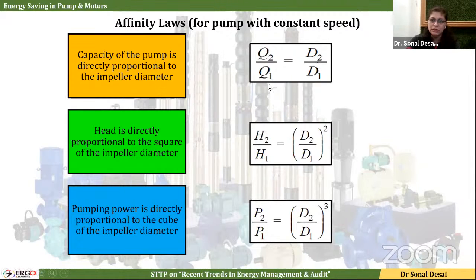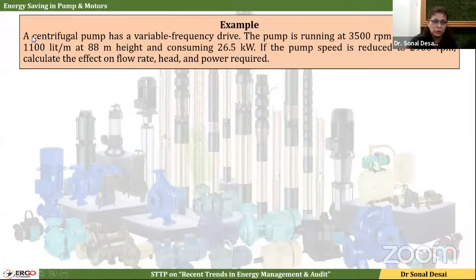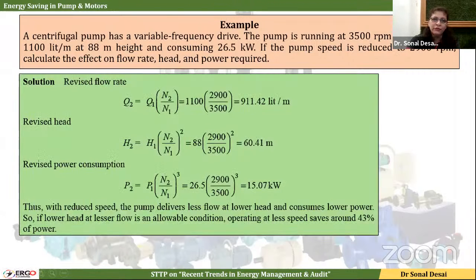If we reduce the diameter, the flow will be varied by a little, but it will have a huge, significant effect on the power consumption. We will see this with the help of an example also. So let us say that there is a centrifugal pump which has a VFD. Let us talk of speed variation first. This VFD based pump is running initially at 3500 RPM, delivering 1100 liters per minute of flow and giving 88 meters of head. For that, power consumption is 26.5 kilowatts. These are the initial running conditions.